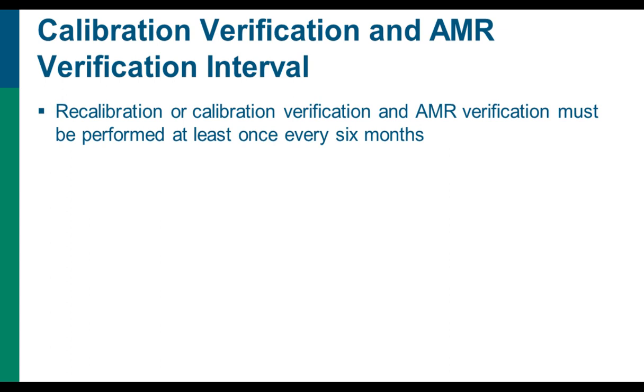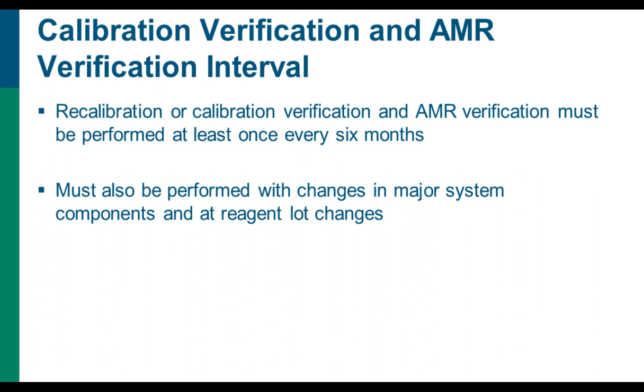As far as the interval or how often you have to do this, calibration verification and AMR verification must be performed at least once every 6 months. So if you can on your instrument store a standard curve, you can store it for up to 6 months or longer if your calibration verification is successful. You also must perform calibration verification and potentially AMR verification when there's any change in major system components. So if you have an engineer come in and replace a part, for example, and also at reagent lot changes.